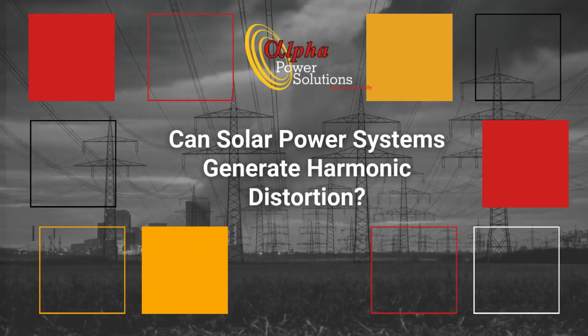Usually when the harmonic content is very high, you will see that there are a number of strange symptoms in a particular site. What's more important is to actually know what the harmonic current is as compared to the fundamental current, and then verify whether or not there is a problem.